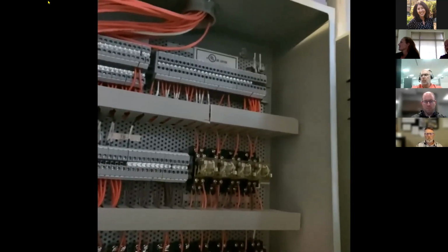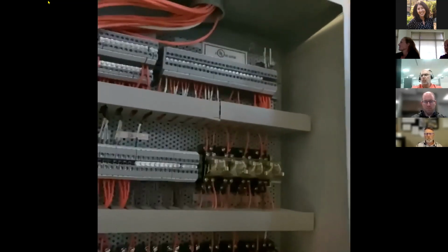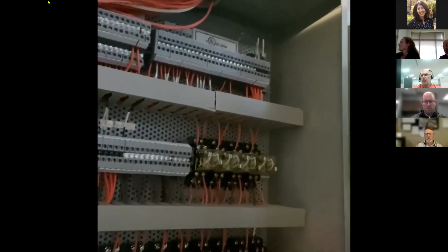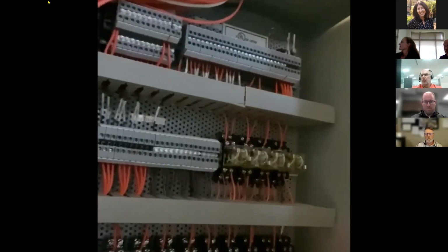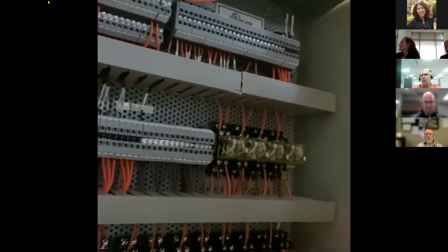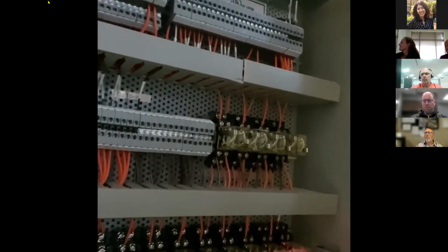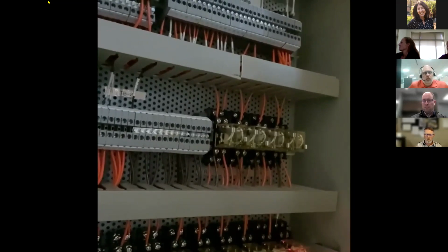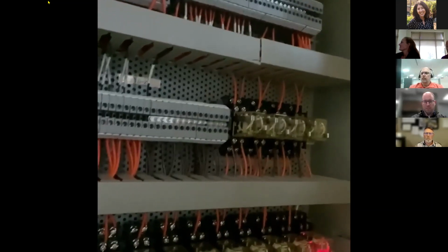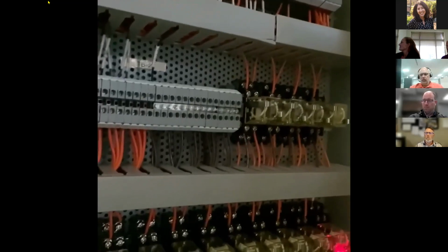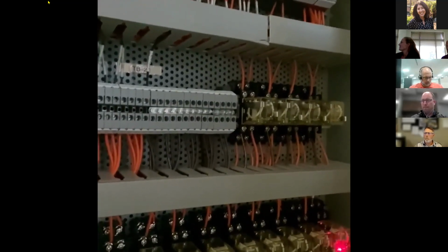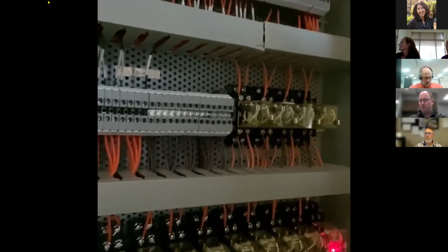The red light is the safety light, so when we do our little experiment here, we'll see the red safety light go off, and then we'll see one of the other red lights going on for the freezestat element that tripped. And we have gone through the energy management system so that we'll know that position, relay number X or whatever is associated with freezestat element number coil A-2, for example.